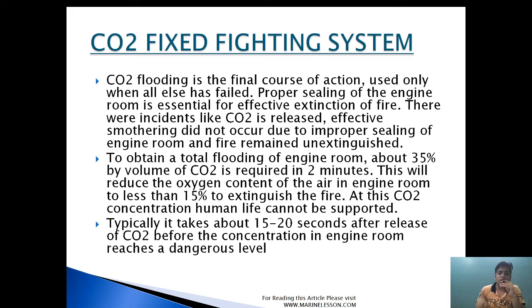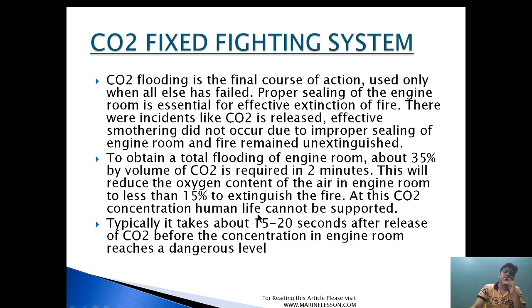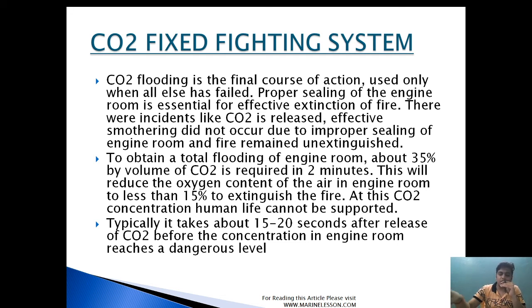CO2 flooding is the final course of action — it should only be used when all other means of extinguishing the fire have failed. Proper sealing is very important. To obtain total flooding in the engine room, approximately 30 percent by volume of CO2 is required within two minutes, reducing oxygen content to less than 15 percent to extinguish the fire. At this CO2 concentration, human life cannot be sustained. Approximately 85 percent of the total CO2 amount, or 35 percent of the engine space volume including casing, must be injected within two minutes.